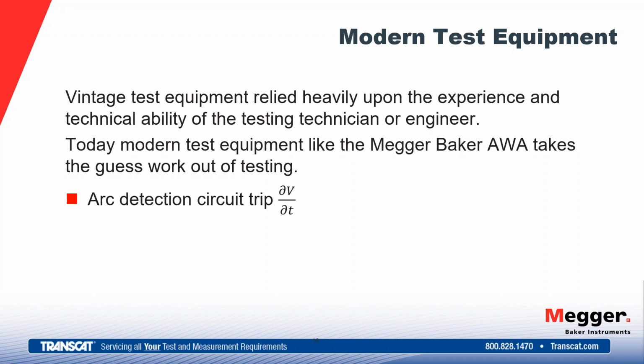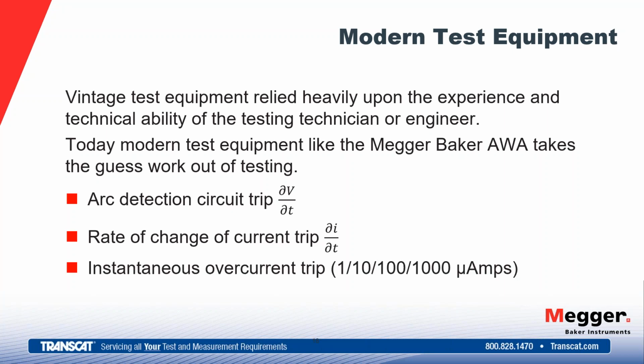So it has an arc detection circuit, which basically is the change in voltage to the change in time. It takes a look at that, and if it detects that arc, it's going to stop the test. It's not going to continue to dump that energy into that fault. So arc detection, the rate of change of current. Again, the hardware is watching current. If the current rapidly increases, it's going to trip the tester and stop the test and not continue to dump energy into that carbonizing type of fault.